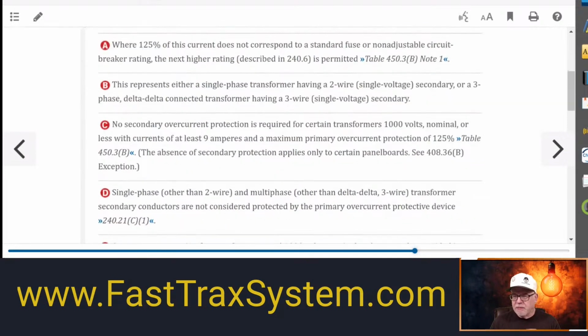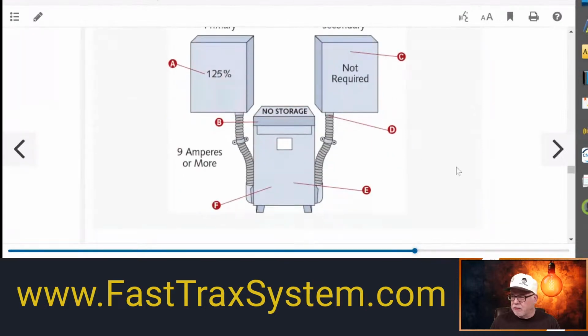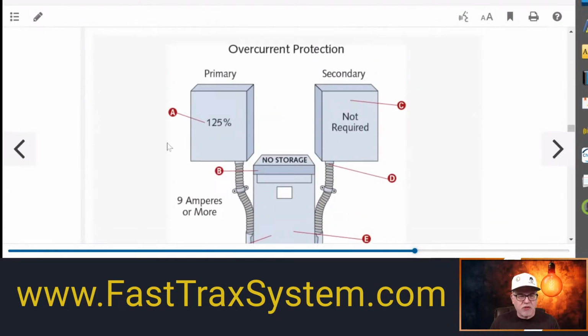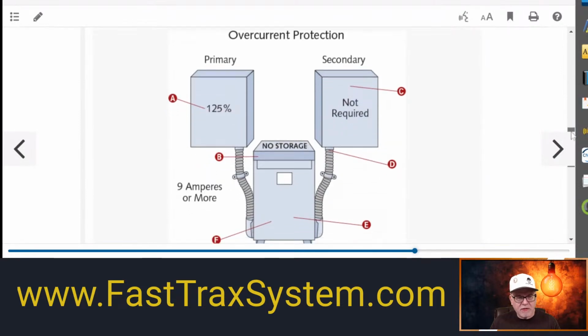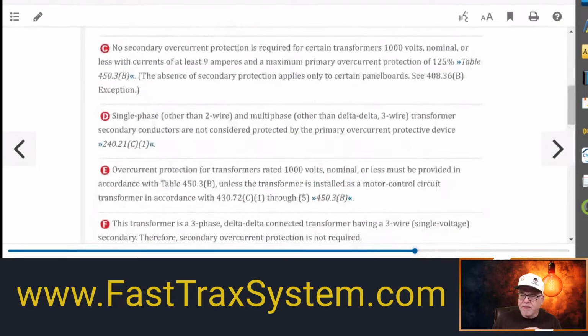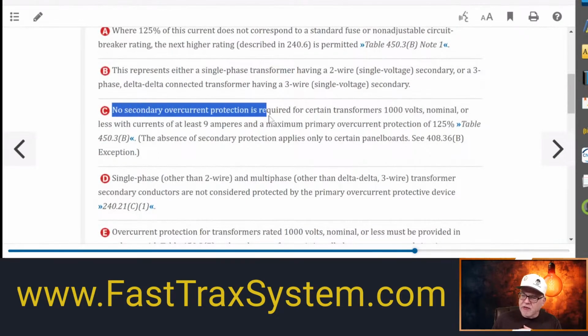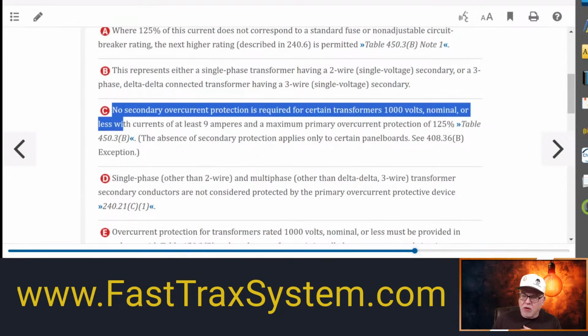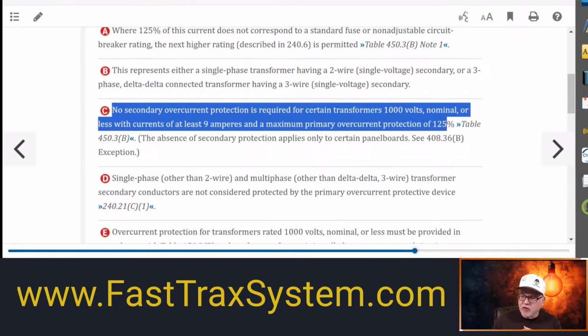All right, so let me make sure I give you an example. Okay, so here we go. I wanted to show the illustration. It's easy for me to show an illustration, and I'm trying to get you both in here the best I can. Okay, so if we have primary only protection and we can meet all those rules, then we can go up to 125% on the primary, and it would not be required to have any protection on the secondary. As with our program, you see C is this callout. It says no secondary overcurrent protection is required for certain transformers at 1,000 volts nominal or less, with currents at least 9 amps and a maximum primary overcurrent protection of 125%.